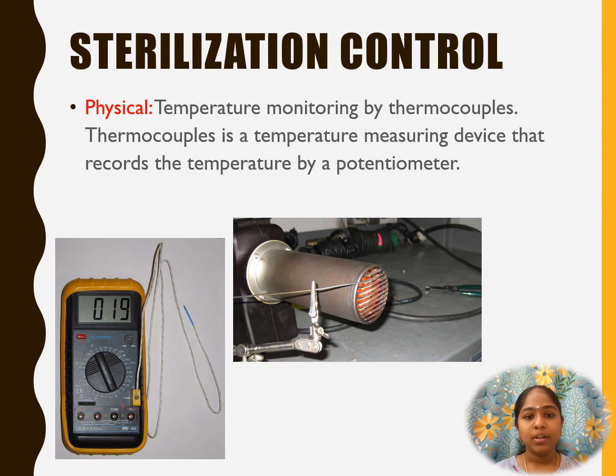Sterilization control. The effectiveness of the sterilization done by the hot air oven can be monitored by physical, chemical and biological methods. The physical method, temperature monitoring by thermocouples. Thermocouple is a temperature measuring device that records the temperature by a potentiometer.